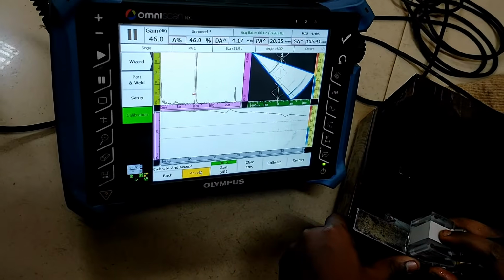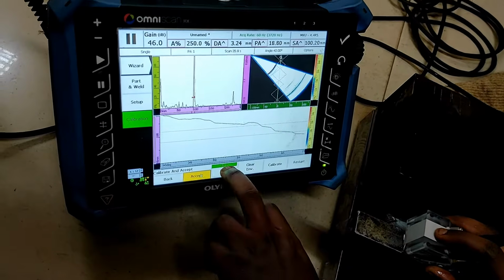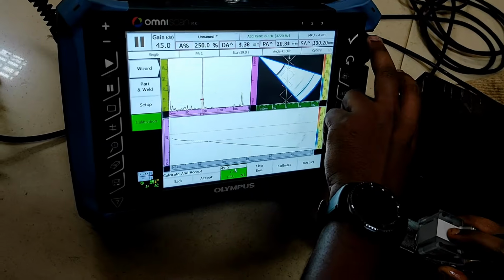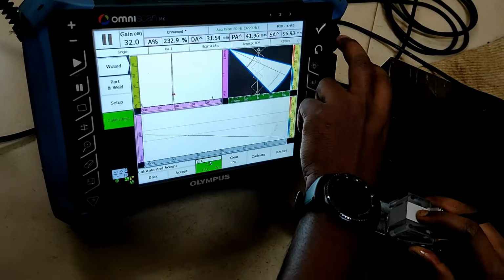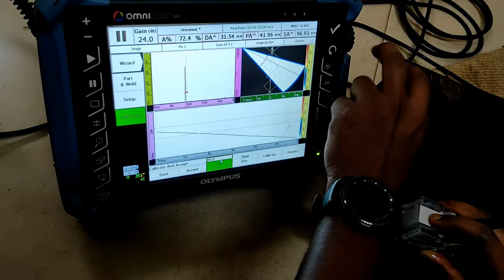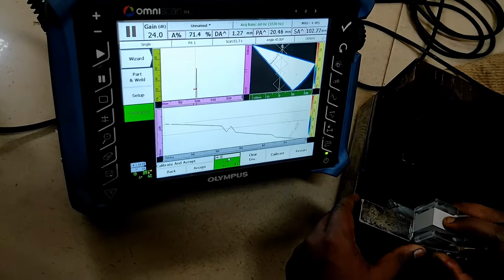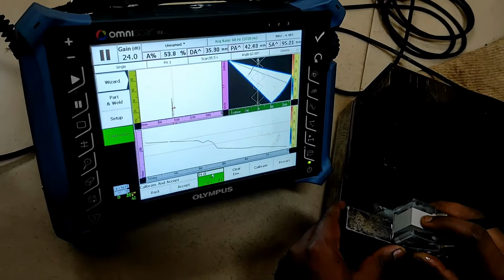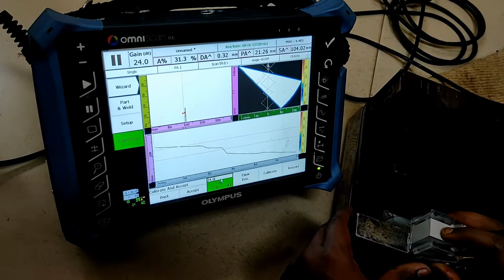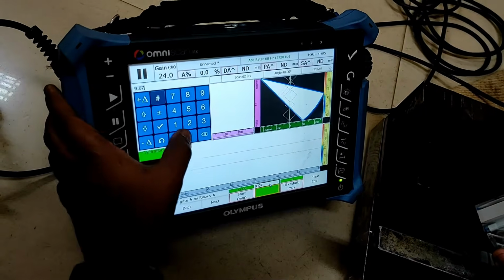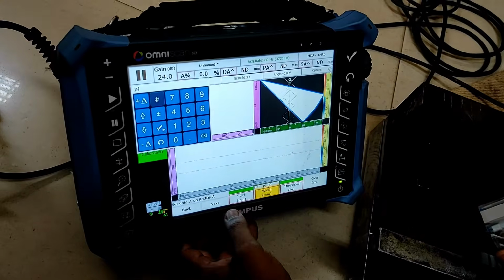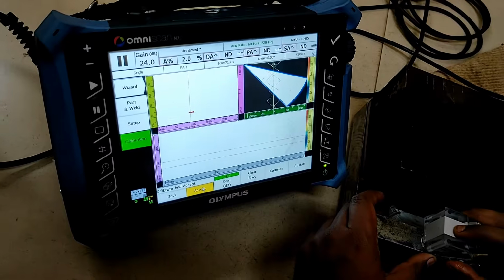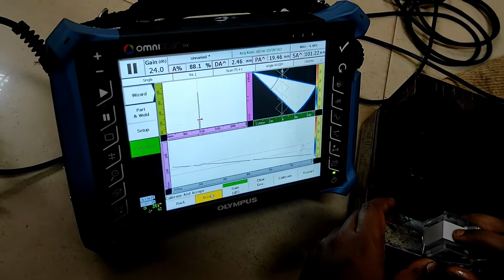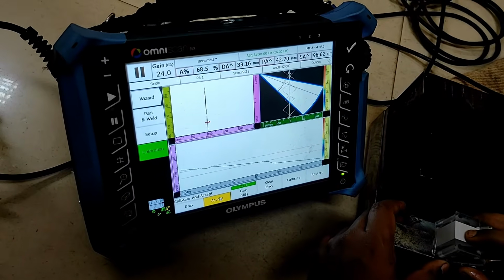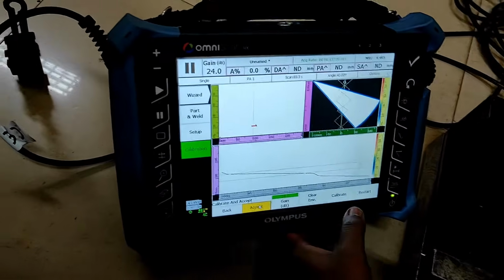Yeah, now we can take the probe and we can go for the calibration. Now the gain is so much high. Sometimes it will automatically take more gain, so we will reduce this gain. Okay, now we will just drag to and fro. Actually the width is little, we have to increase little more with around 15. Now we can go do. Okay, now do one time calibrate.